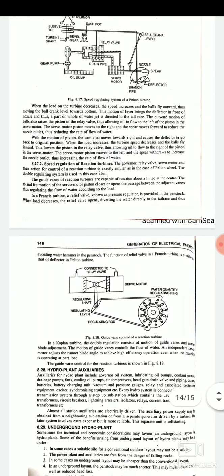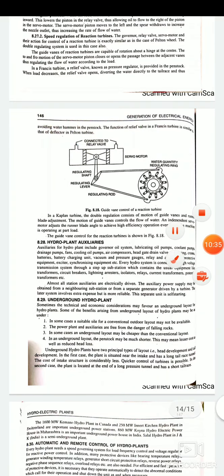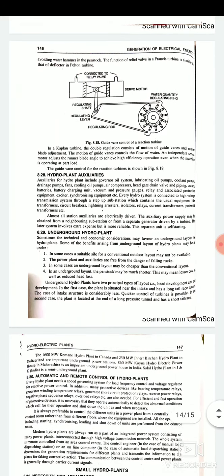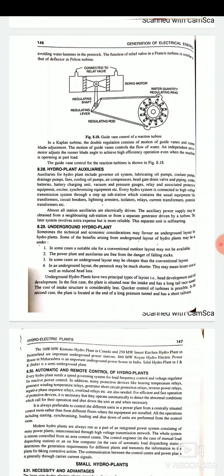Now the speed regulation of reaction turbines. The governor relay valve servo motors and direction for control of a reaction turbine are actually similar as the case of Pelton wheel. The double regulating system used in this case also. The guide vanes of reaction turbines are capable of rotation about a hinge at the center. The to and fro motion of the servo motor piston closes or opens the passages between the adjacent vanes, thus regulating the flow of water according to the load. So this is the guide vanes control of a reaction turbine that is in Francis turbines and in Kaplan turbines. That uses the double regulation consists of motion of the guide vanes and runner blade adjustments.